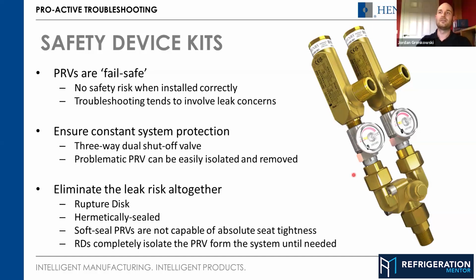Yeah. Okay, cool. Again, we talked about these devices are things that can introduce pressure drops, so it's important to make sure that the three-way valve you're using is correct for the PRV. Again, we've got guidance in our product catalog and on the online selector, as you saw there. I could select different three-way valves. It will tell you which one is adequate. Because again, if you have a three-way valve that's too small, then it's going to restrict the flow, and your relief valve is going to be affected. So important to make sure you use the right one.